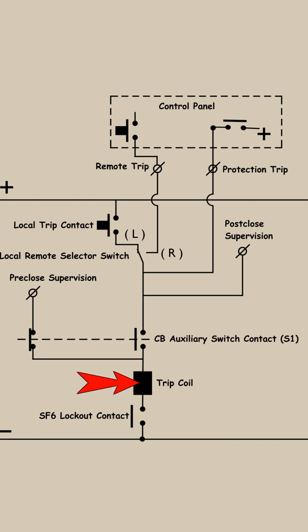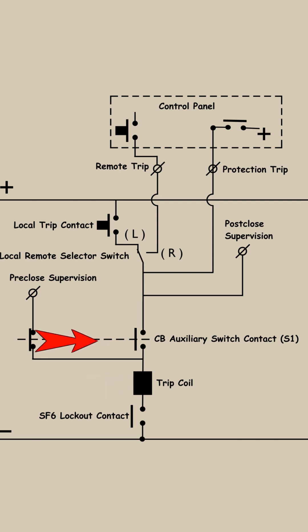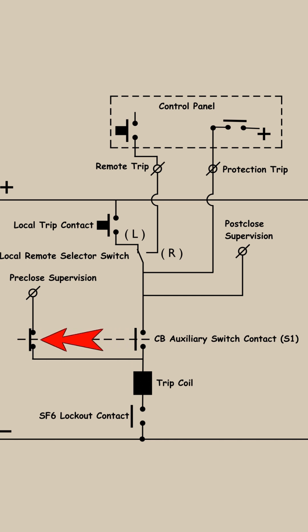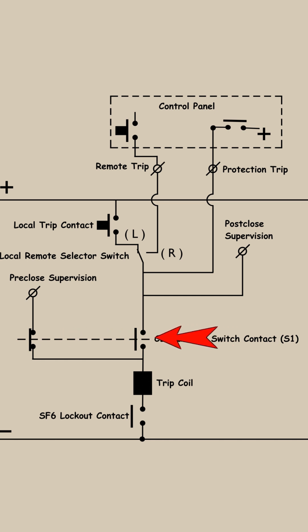Here, you can see the trip coil. This contact is a normally open (NO) contact of the auxiliary switch of the circuit breaker. And this is the normally closed (NC) contact of the auxiliary switch of the circuit breaker. So when the circuit breaker is in the open condition, this switch will be in the open position and this switch will be in the closed position.